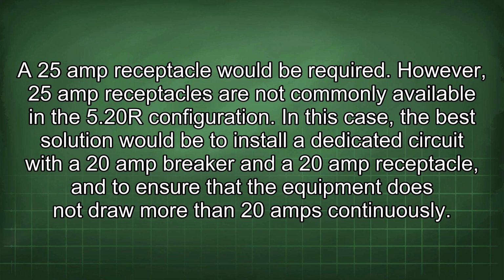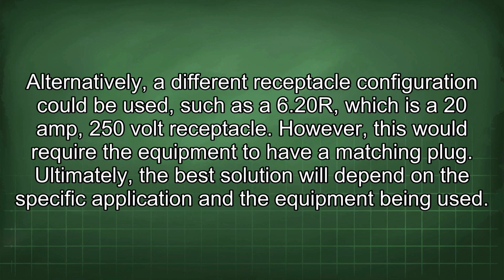In this case, the best solution would be to install a dedicated circuit with a 20 amp breaker and a 20 amp receptacle, and to ensure that the equipment does not draw more than 20 amps continuously. Alternatively, a different receptacle configuration could be used, such as a 6-20R, which is a 20 amp, 250 volt receptacle. However, this would require the equipment to have a matching plug.